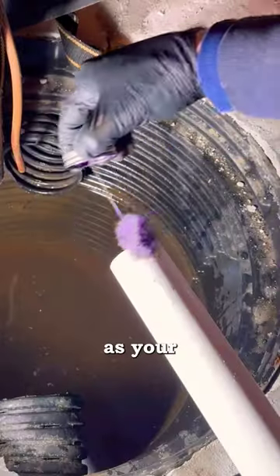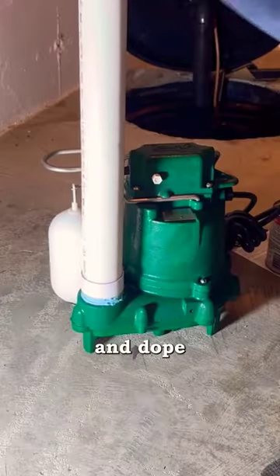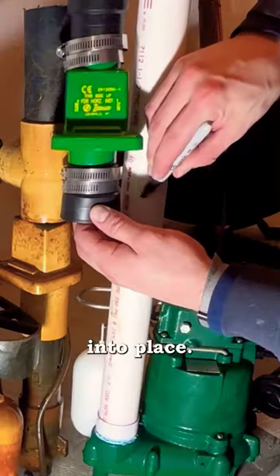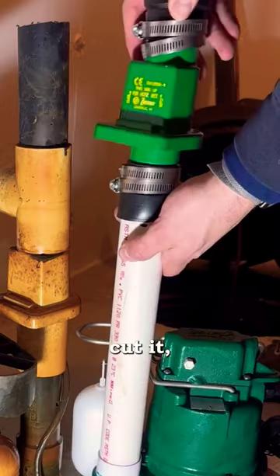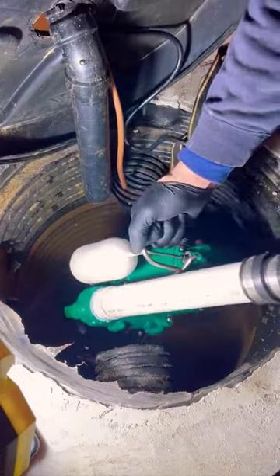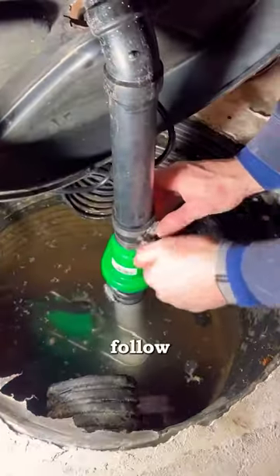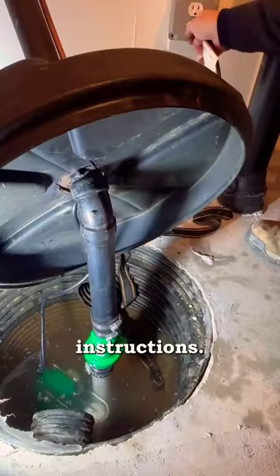Make sure you have the same discharge pipe as your old one — in my case it's inch and a half. I'm adding a male adapter, tape, and dope and putting it into place. I line it up with the old one, cut it, add on my check valve, and poke a hole for my airlock. That might have went by pretty quick, but all the instructions are very easy to follow in the Zoeller sump pump installation instructions.